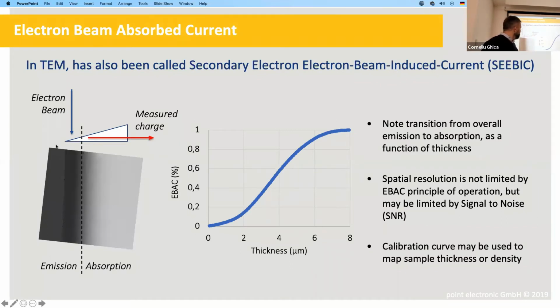What is happening is that when the sample is very thin, we have mostly emitted electrons. The primary electrons go through the sample and they're not absorbed in great proportion. They also excite more electrons and move more electrons out of the sample, and therefore we lose overall electrons from the sample, so we extract electrons from our circuitry. Whereas when the sample is thicker, absorption is dominant, so we have more absorption than emission. If we plot the EBAC signal as a function of thickness, which we can do because it's a wedge, we can see there is a relationship between the two, and there is a saturation and so on.